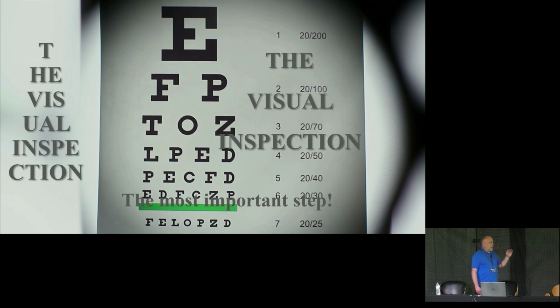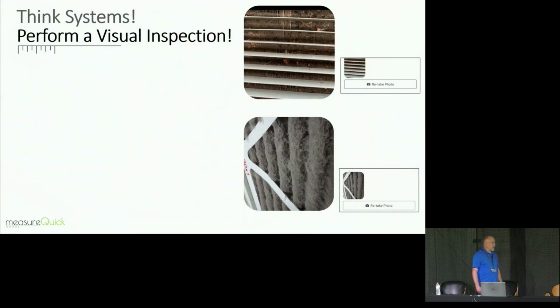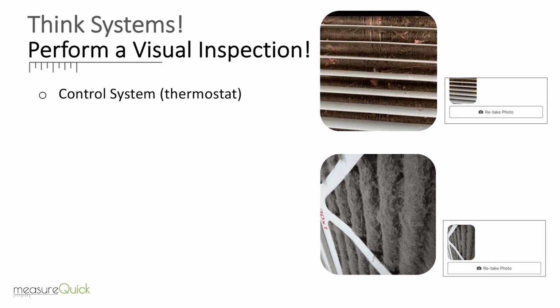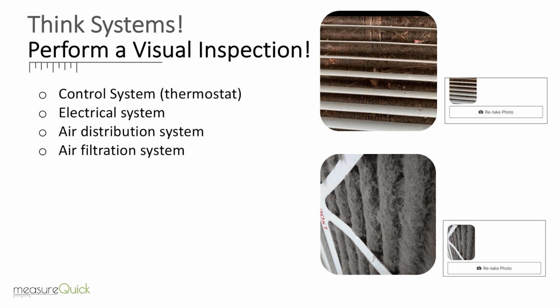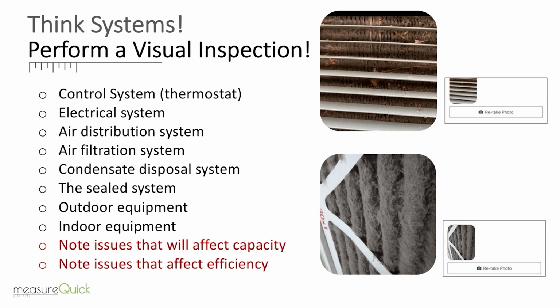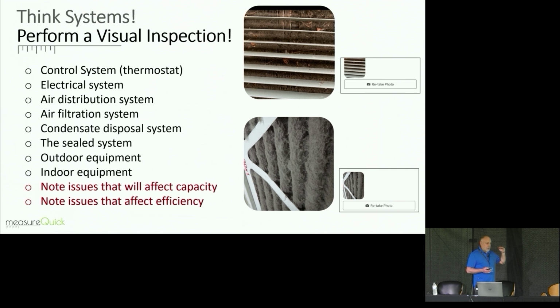And the reason I'm so adamant about some of these things is because if we're not thinking about systems, right? I get caught up here, right? The control system, the electrical system, the air distribution system, the condensate disposal system, right? Filtration system, the sealed system, our outdoor and indoor equipment. If we're not looking at this from a system approach, we're missing a lot of valuable information about that unit, right? Because if we're just going to swap a box out, we're going to end up with a lot of problems that we're going to overlook.